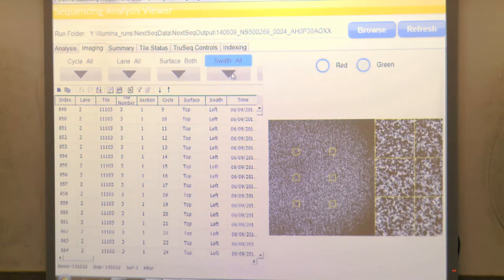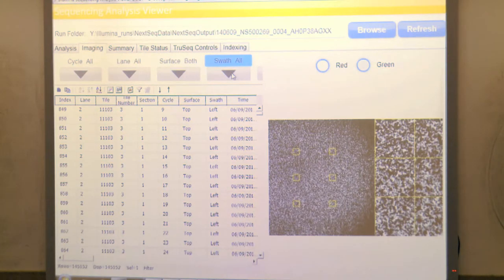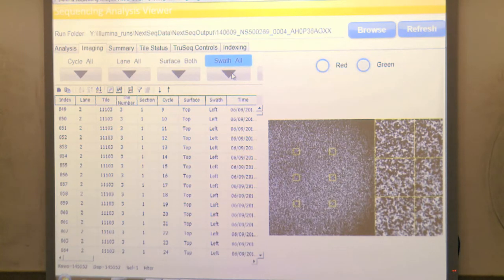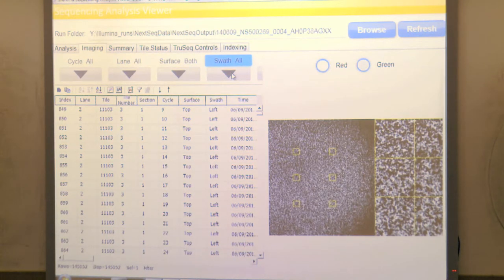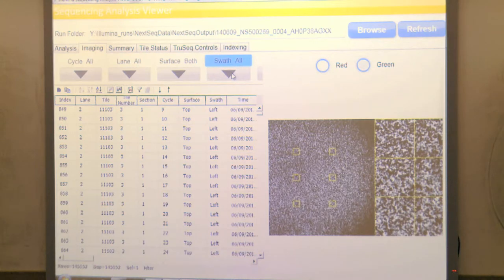What are the sizes of these run data files? We don't save the raw image files because they're too big. The computers attached to the instruments don't have much memory - a HiSeq computer is about two terabytes, with one terabyte each for the A and B side (since HiSeq can run two flow cells simultaneously). The images reviewed in SAV are thumbnails - small files.